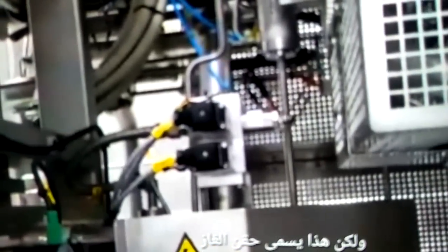So when this valve opens here, we pump into the tank. Then we have another valve here, but this is the spraying valve. And then around the other side, we can't see them from here, are the safety valves for the air. Okay, the two valves for air, spraying safe. So this setup here is for here. The one below it is exactly the same as this one, but this is for gas injection, because we need to sterilize the gas injection pipe. So this one here, exactly the same concept, at exactly the same time.